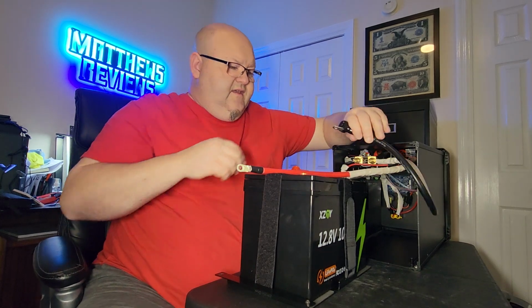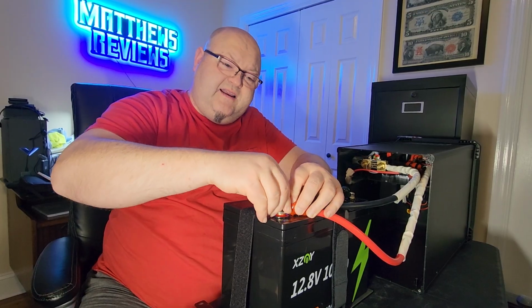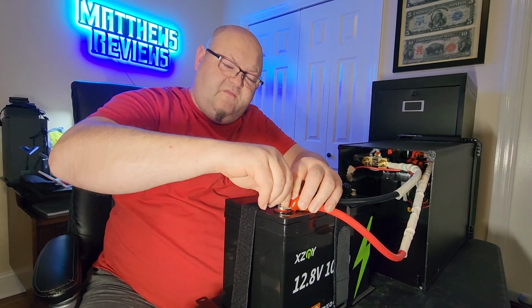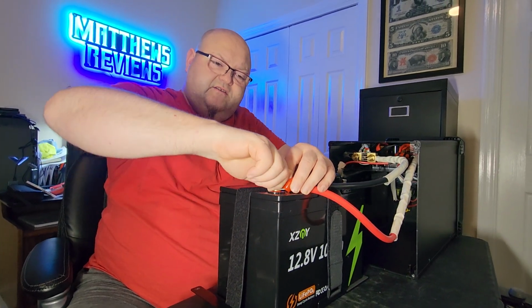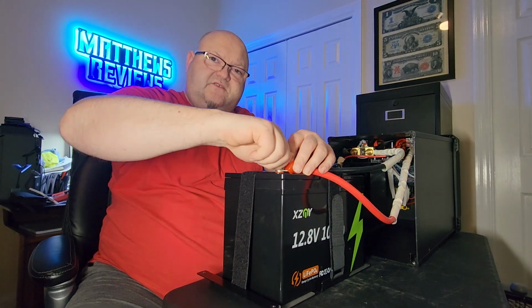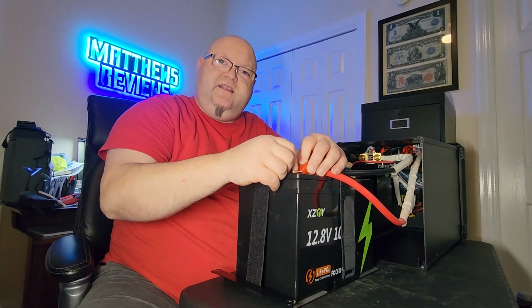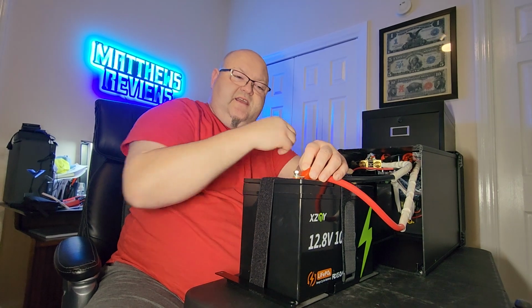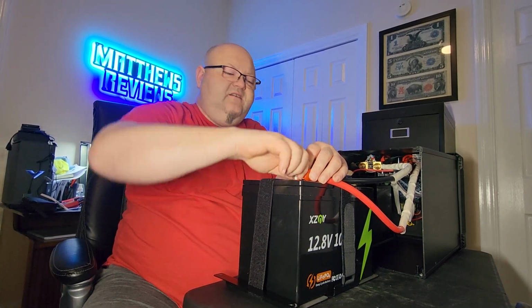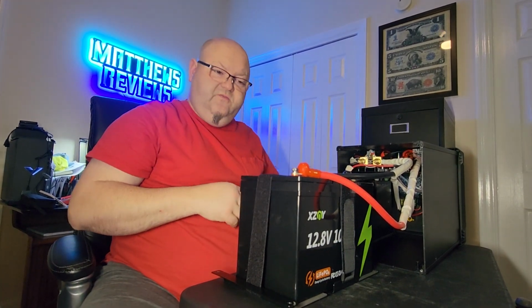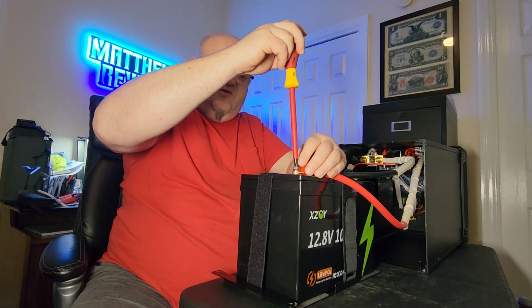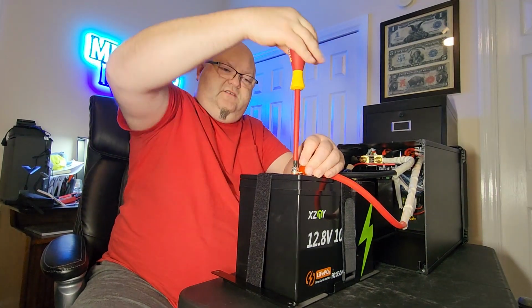Then you go ahead and get them connected. Now keep in mind, I didn't have to use a resistor before I touched the cables to the battery, simply because I disconnected the battery with the disconnect switch on the front of the unit. So when you do that, there's no way to create a spark. So you just tighten it up.